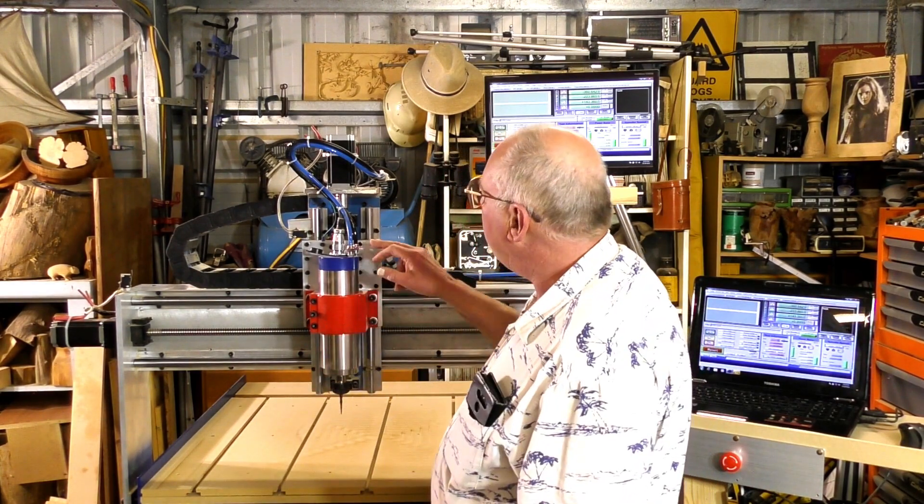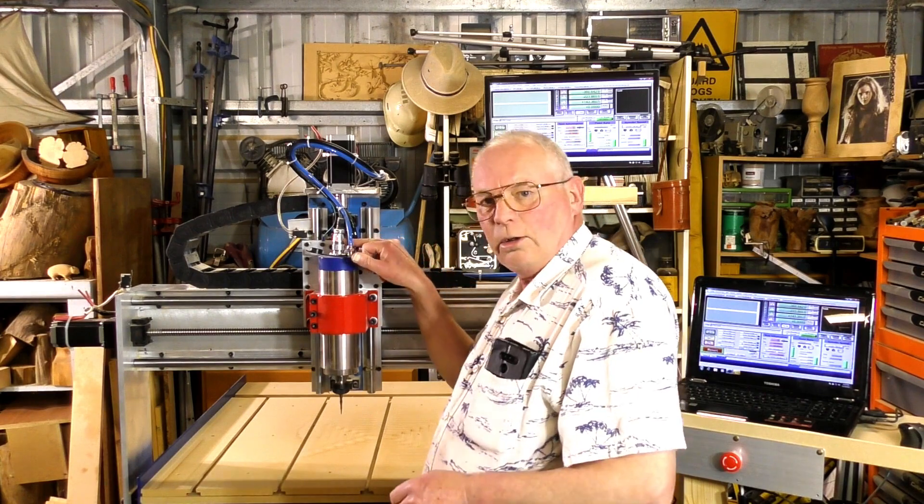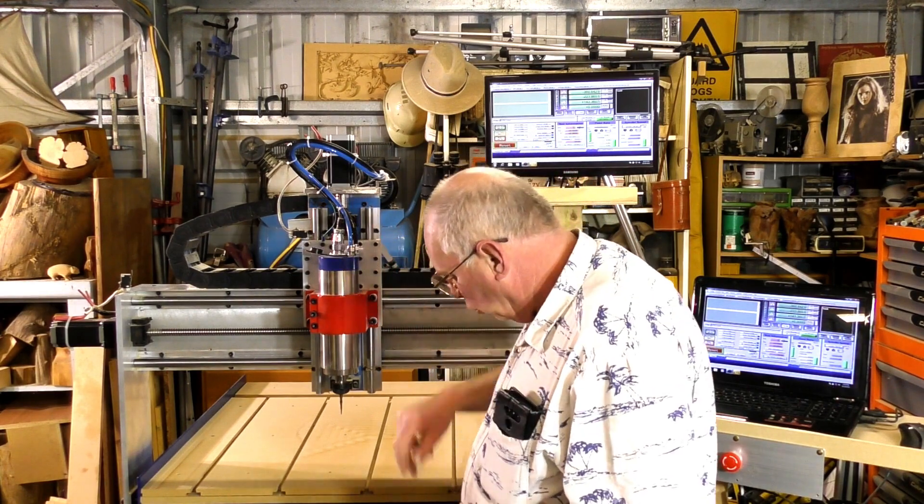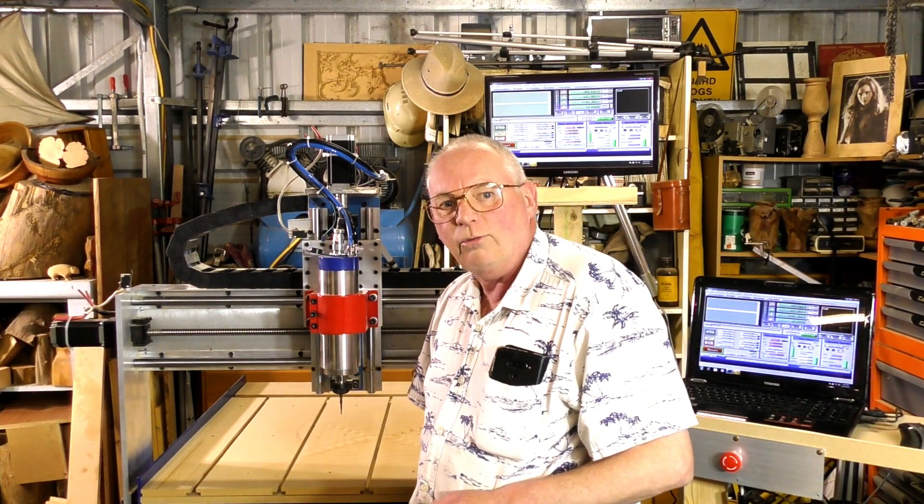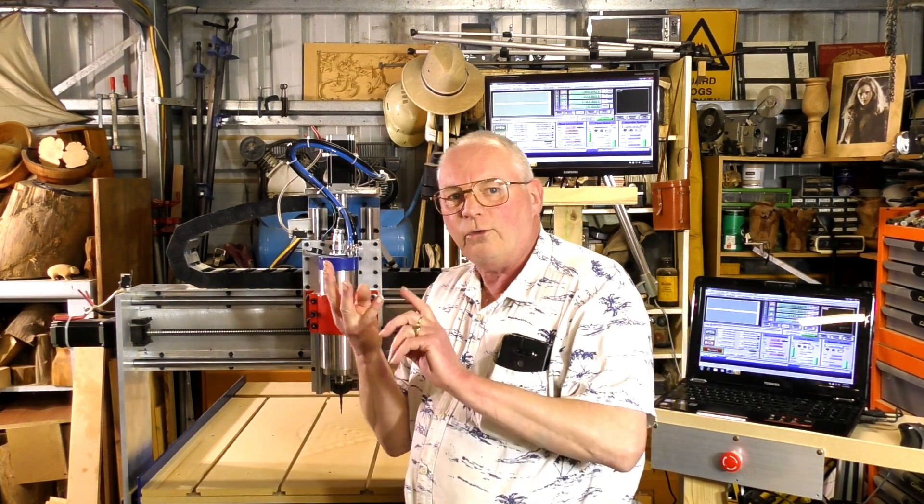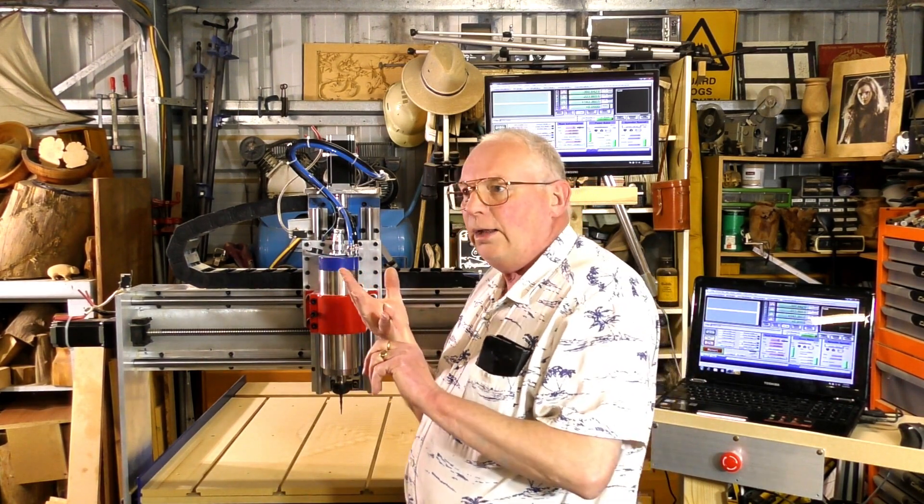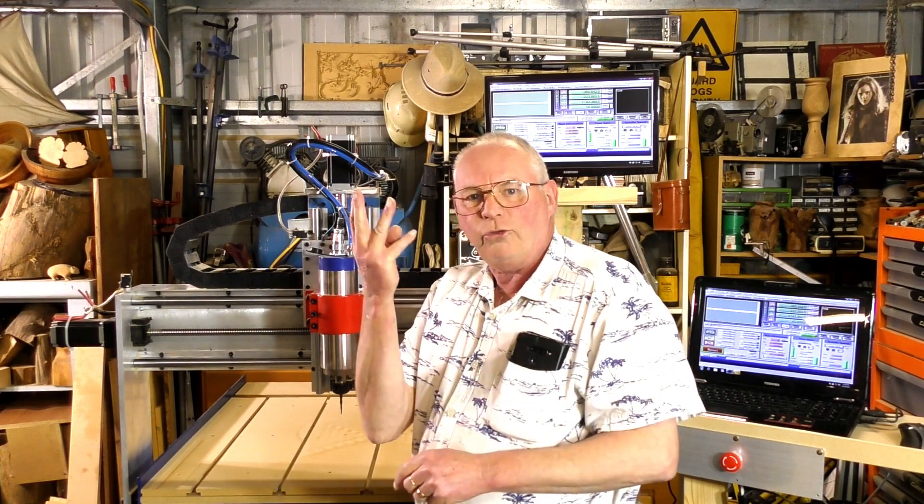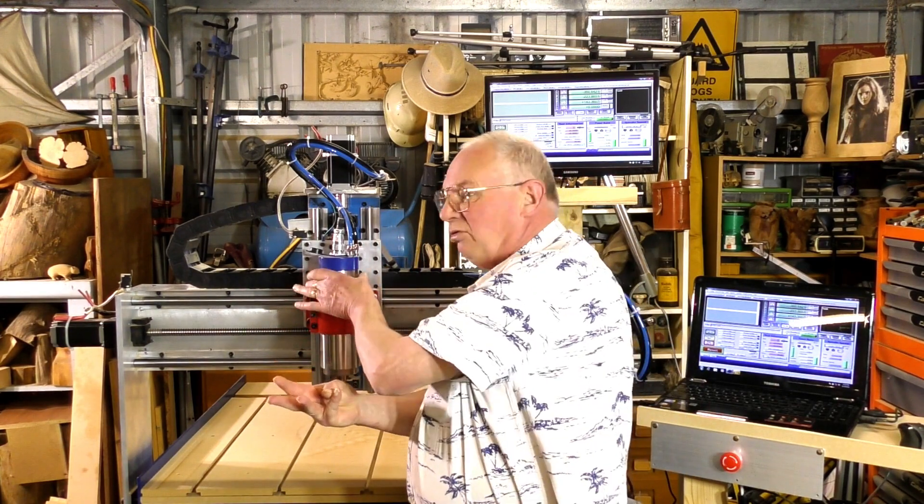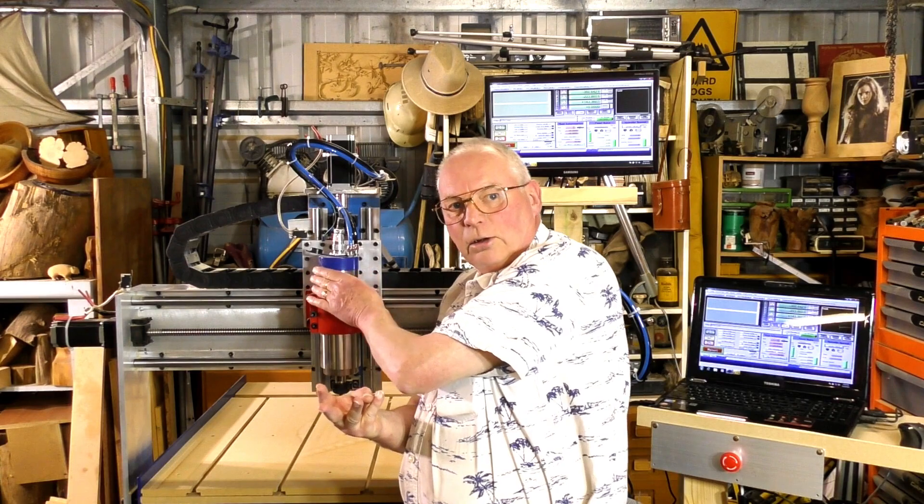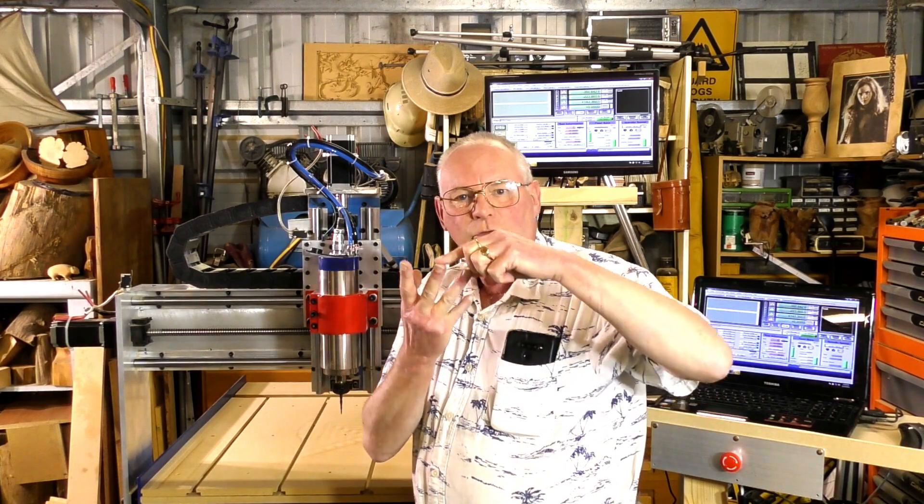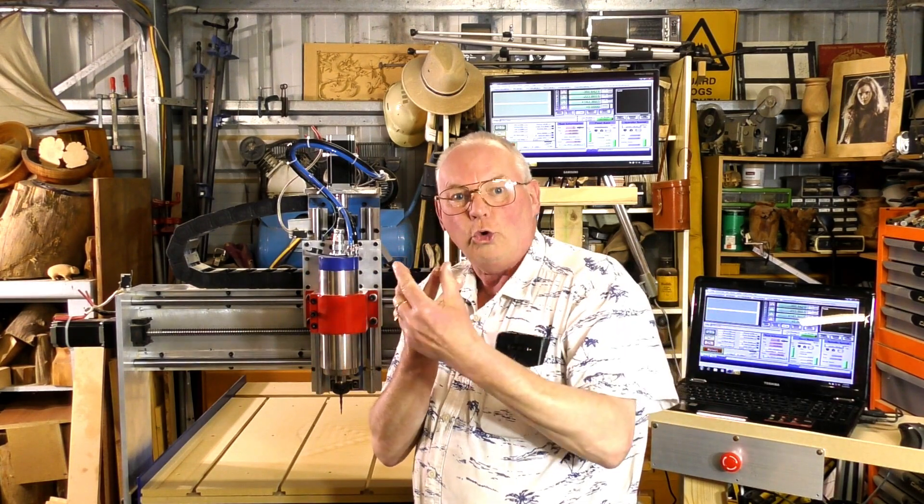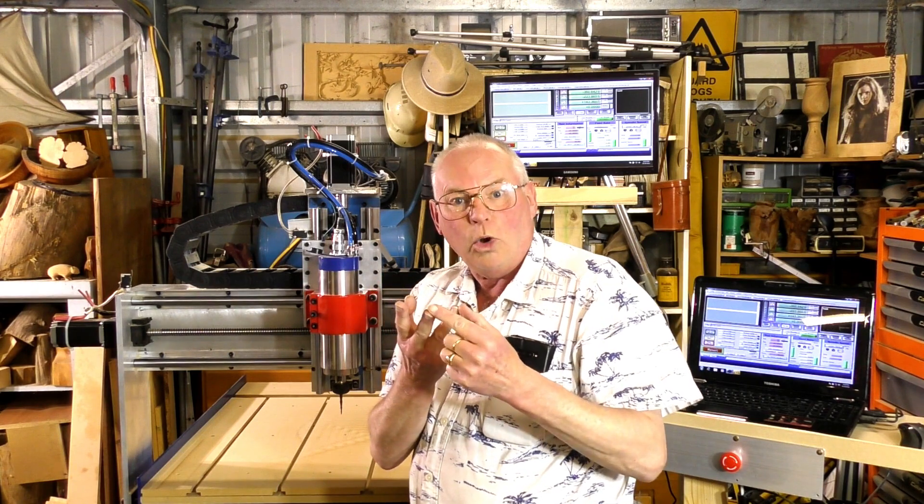Now, you can either change the wires up here, or the wires on the VFD. There are four wires. There's an earth, and there's three poles of the three-phase spindle. Change any two of the pole wires.